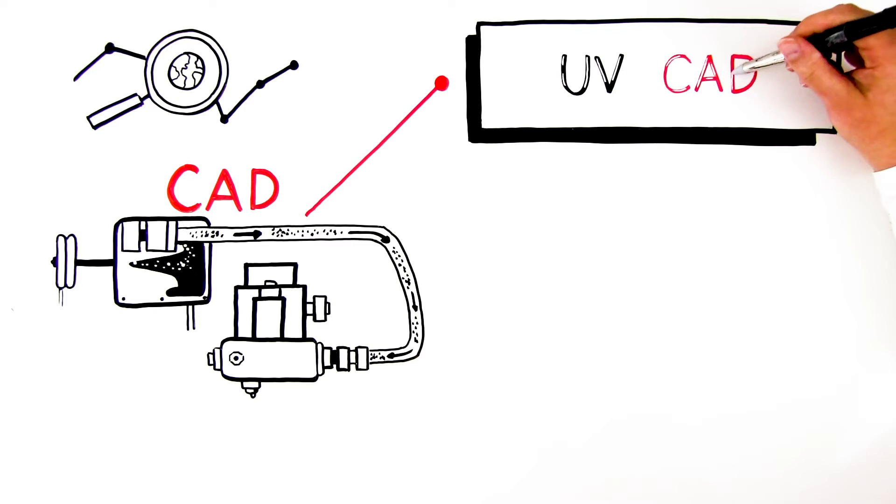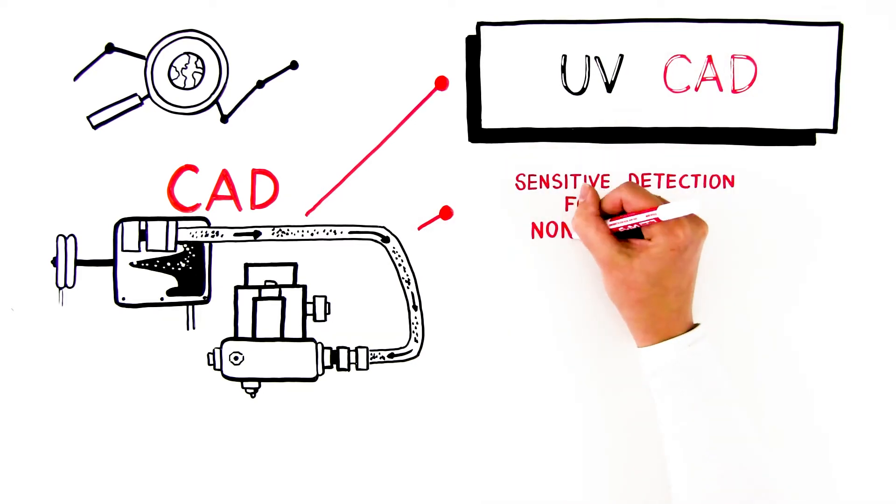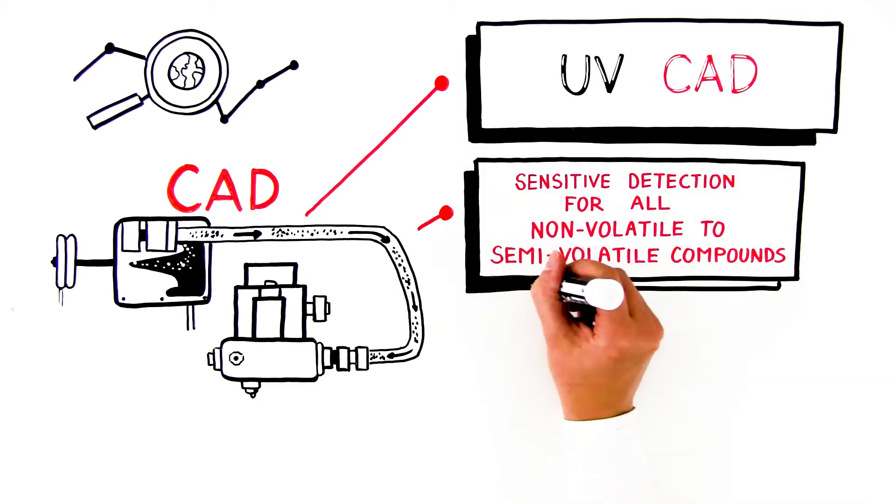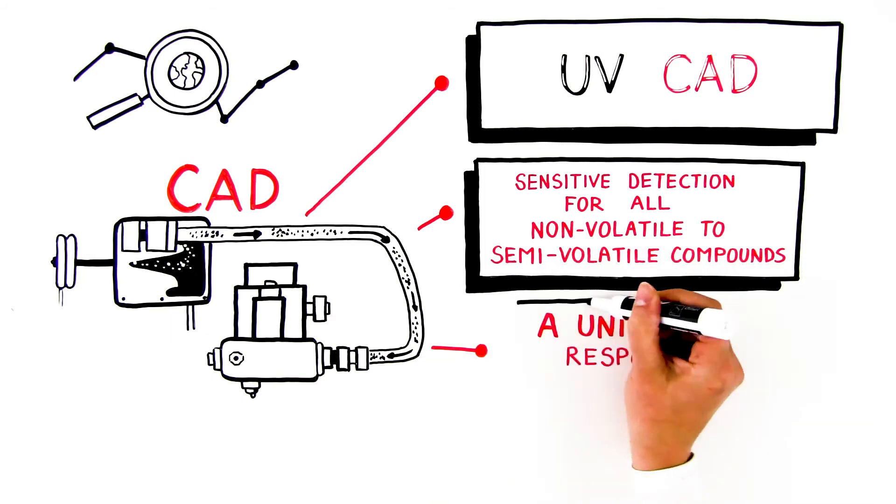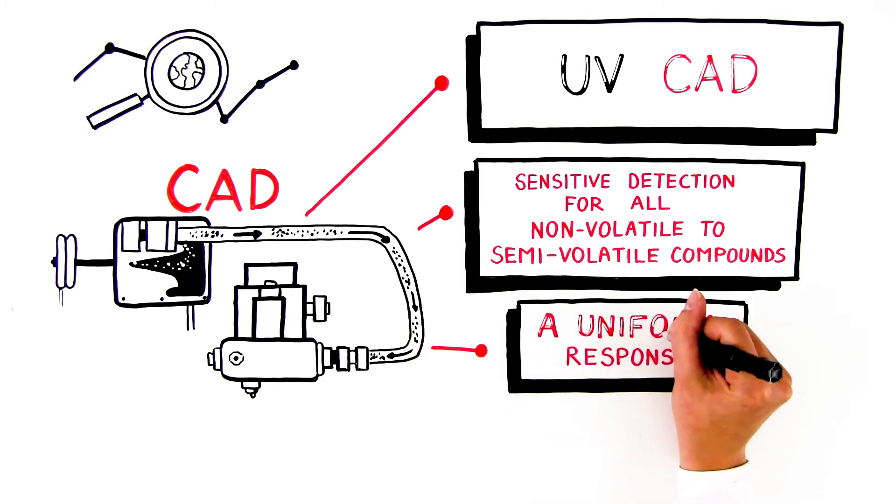CAD also provides sensitive detection independent of whether a chromophore is present or not, unlike UV, or whether the compound forms gas phase ions, unlike MS. A uniform response, as in the ability to obtain similar response for all components regardless of analyte structure.